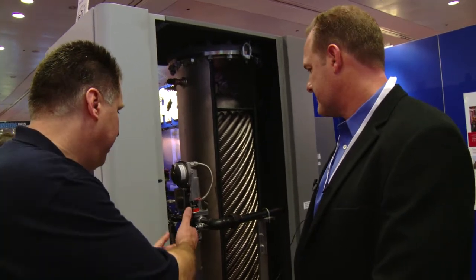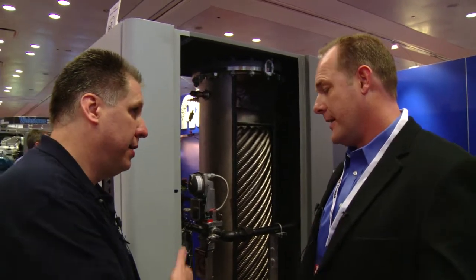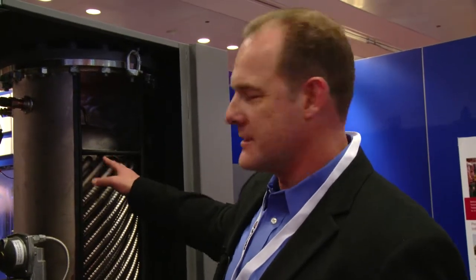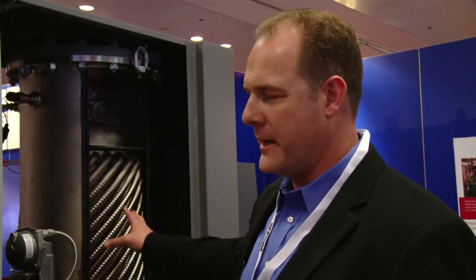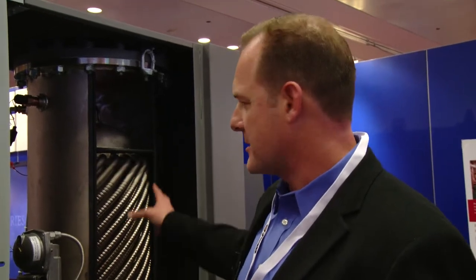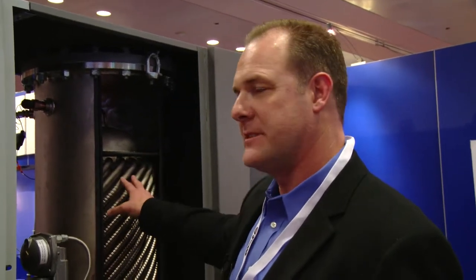Harold, what's your experience with this product in a hard water situation such as we have in the DC area? Right. There are several areas around the country with hard water conditions where lime and scale can build up on a heat exchanger and eventually cause a premature failure. But the combination of having a stainless steel heat exchanger and this unique baffle design with a very small fractional horsepower circulating pump always keeps a certain amount of water circulating over the tubes, which doesn't allow any precipitates to precipitate out on the heat exchanger, which would cause a premature failure.